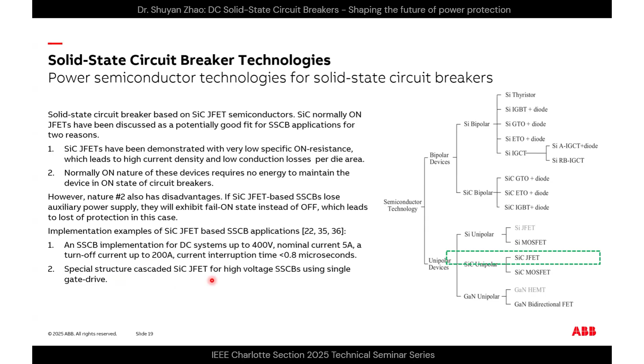Implementation examples of JFET-based solid breaker applications exist in several works. For example, one work shows a solid breaker for DC systems up to 400 volts nominal voltage, 5 amps -- relatively lower, but a preliminary concept I think -- with turn-off current up to 200 amps and current interruption time less than 0.8 microseconds. There are also special structures called cascaded SiC JFET for high voltage SSCB using a single gate drive.